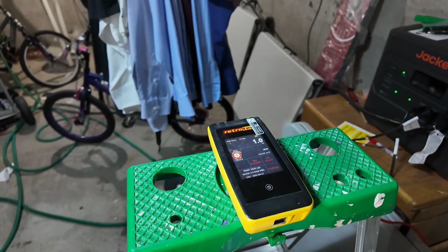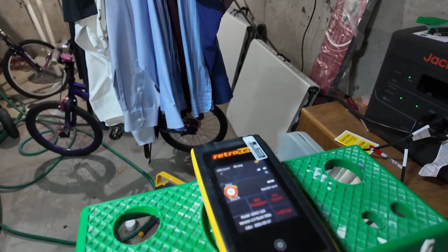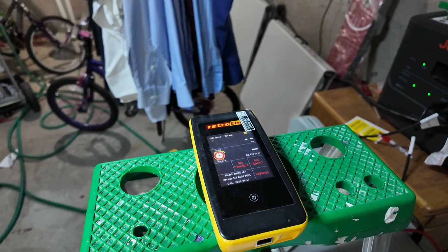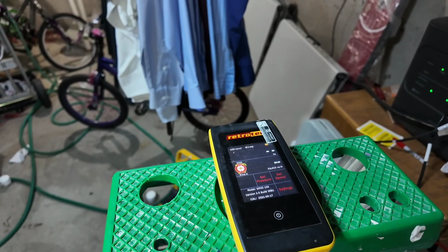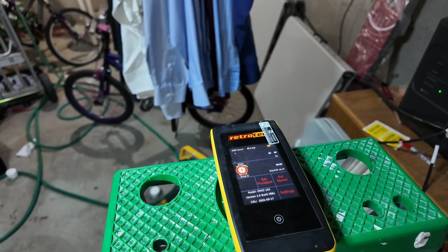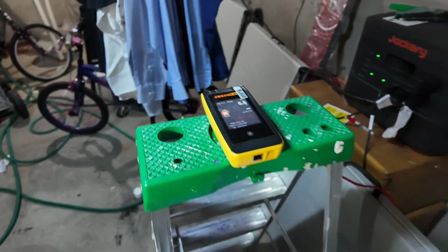And at this point, we are reading a positive 0.3, positive 1. It appears as if we've got a slight wind outdoors. So I will set the baseline averaging to 30 seconds. That's a 30-second average, so we should get a fairly accurate number. And a positive 0.5 or 0.6, positive 0.6.